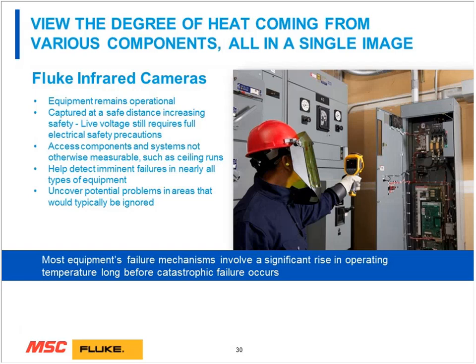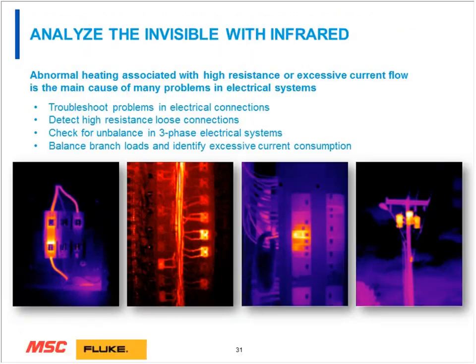Also, infrared cameras. Infrared cameras, extremely important. They're really your front-end tool to go ahead and scan a surface and try to find out what is going on. There's a couple ways to use these. One is qualitative, another is quantitative. Most of the time, all you do is scan the surface to look at a qualitative measurement. In other words, focus on the area that is hot. That'll indicate excessive current, a loose connection, or some other issue that you really need to pay attention to.